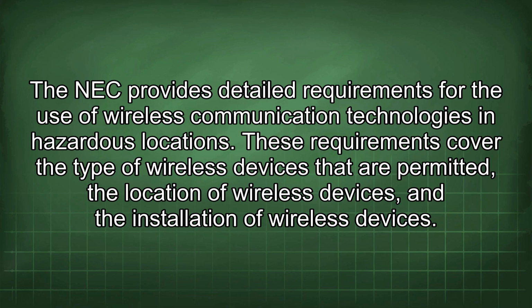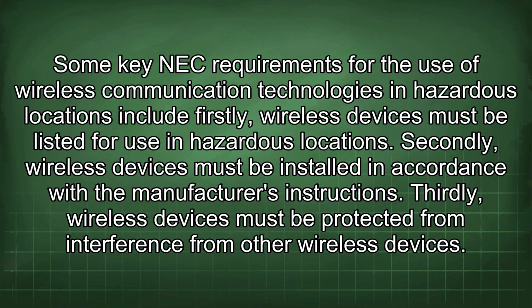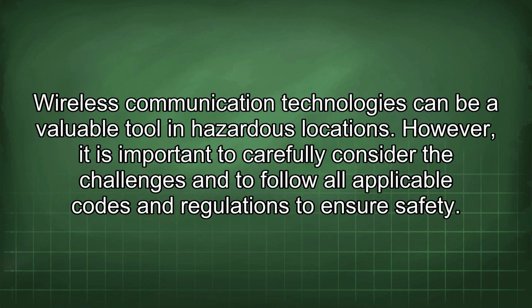The NEC provides detailed requirements for the use of wireless communication technologies in hazardous locations. These requirements cover the type of wireless devices that are permitted, the location of wireless devices, and the installation of wireless devices. Some key NEC requirements for the use of wireless communication technologies in hazardous locations include: firstly, wireless devices must be listed for use in hazardous locations. Secondly, wireless devices must be installed in accordance with the manufacturer's instructions. Thirdly, wireless devices must be protected from interference from other wireless devices. Wireless communication technologies can be a valuable tool in hazardous locations. However, it is important to carefully consider the challenges and to follow all applicable codes and regulations to ensure safety.